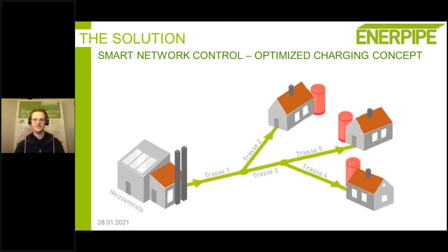You can see it here as well, the different colors are different houses, and when you see a peak, the motor valve is open to charge the buffer. On the left-hand side it's uncontrolled loading, so every buffer can be loaded if there's demand. On the right-hand side there's a controlled charging concept, so if one house needs heat, I will charge other houses as well, giving an opportunity to switch off the pump for a certain time.